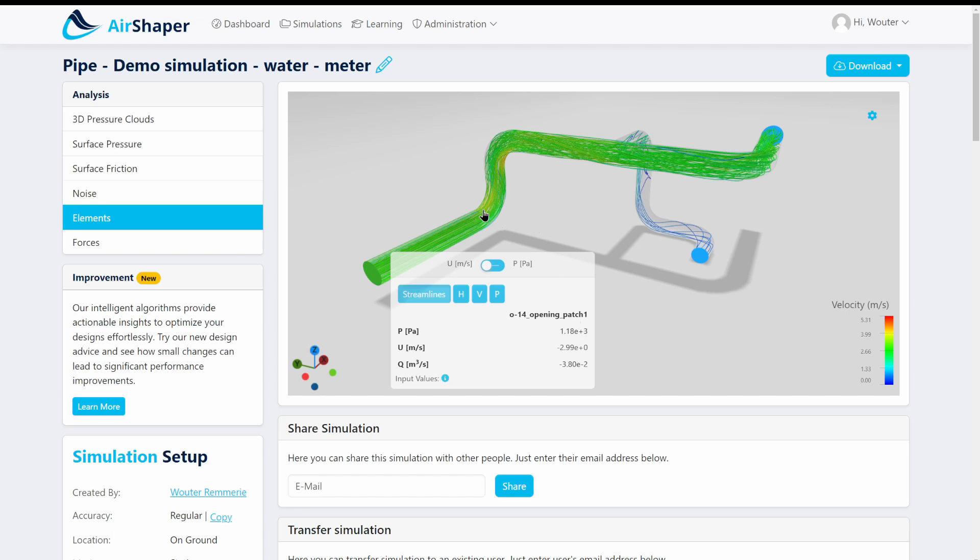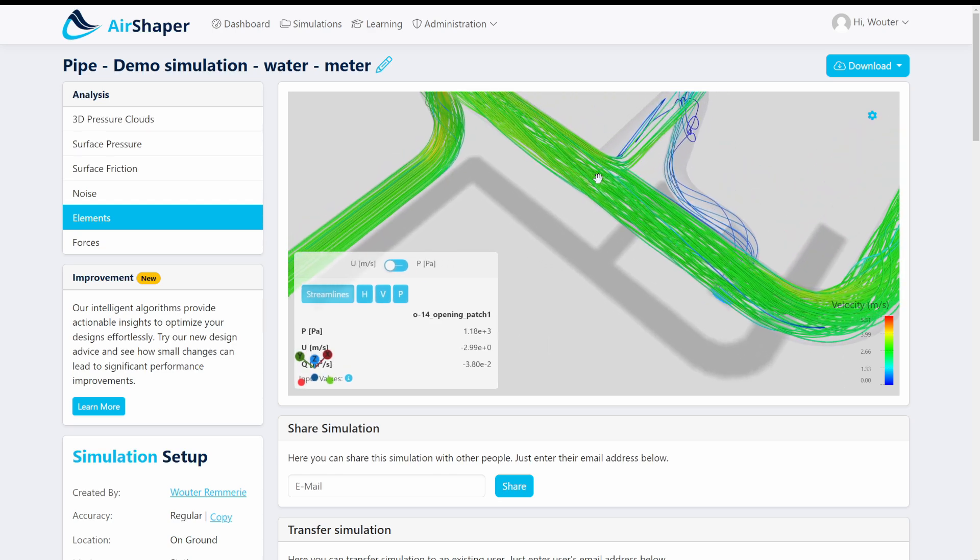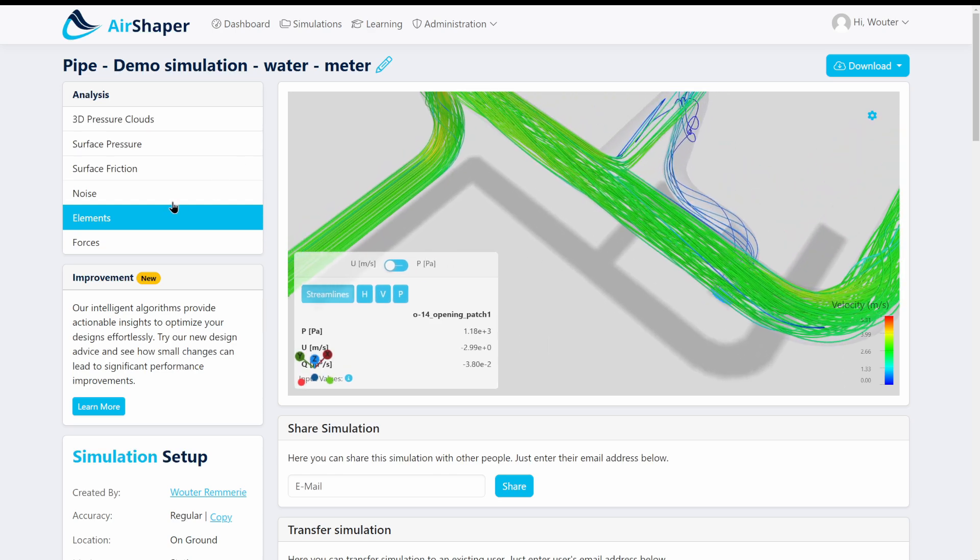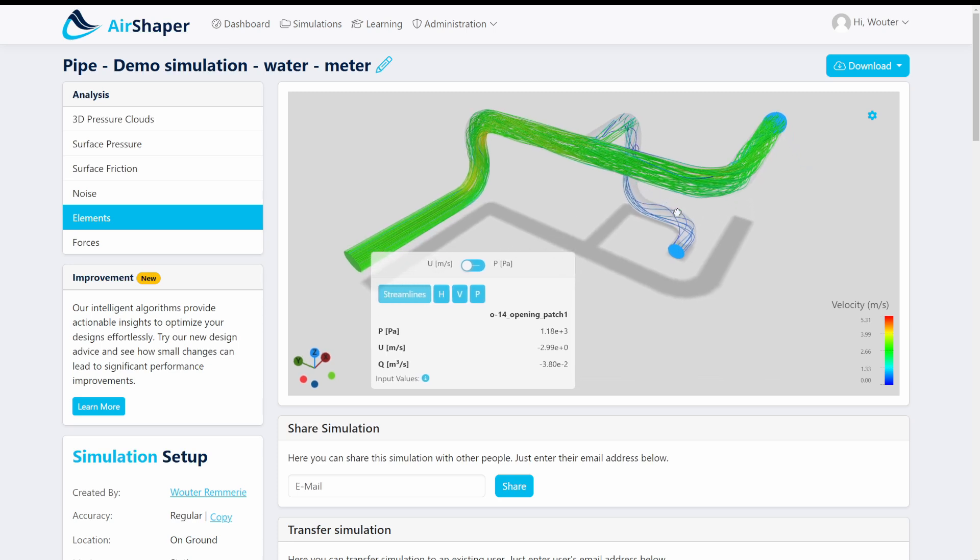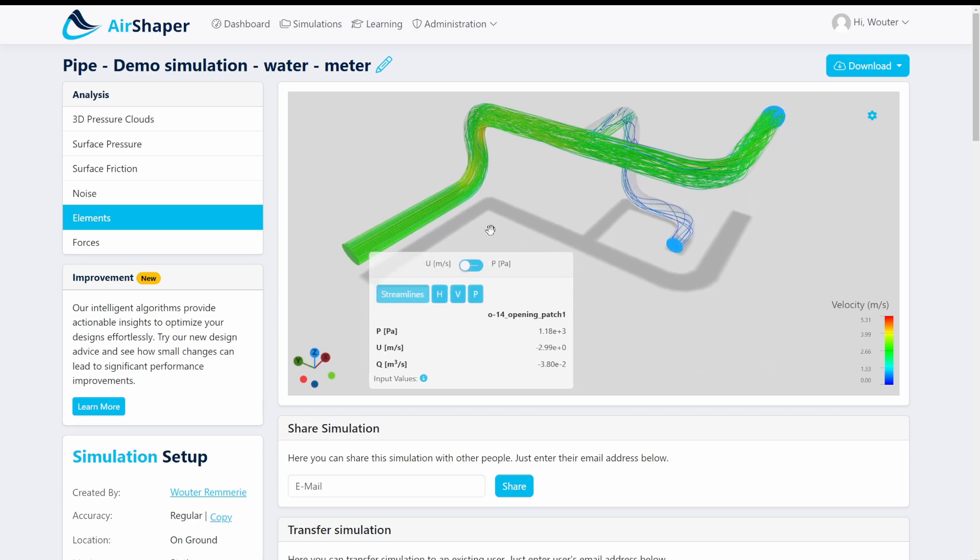And if you were to optimize these elements, a different radius, larger radius perhaps or starting your curve here already or having one 3D curve between these elements instead of these two 90 degree bends, and if you would optimize this system this area then you would greatly reduce the pressure drop.